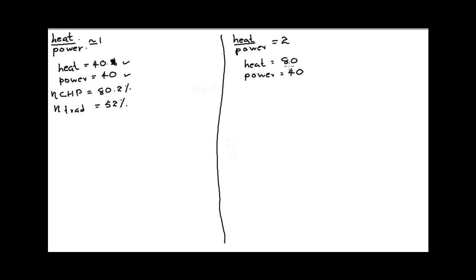But our requirement now is 80 heat units and 40 power units. We could use 2 diesel engines — then we would get 80 heat units and 80 power units. However, since the diesel engine's target is to provide power and heat is recovered as waste, if we use 2 diesel engines then we are losing 40 energy units. Therefore, that is not going to be a suitable solution.